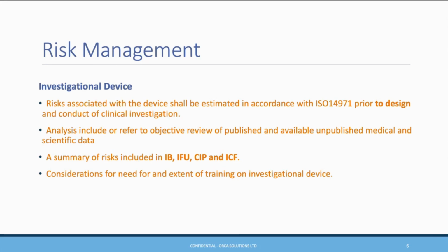The other element that we have to be mindful of, which we've already been thinking about, is around the device itself. What we've been asked now is to actually look at the ISO 14971, which is our risk management or risk assessment for the actual device itself, and look at how we may take in the nature of running the study, how we're taking that device and maybe using the device in a slightly different way. Because certainly if you're pre-market, your final device may be a very early iteration, it may be a prototype, it might not be the final version. And so we have to look at the actual ISO 14971. And then we also have to look at what we're going to do differently.